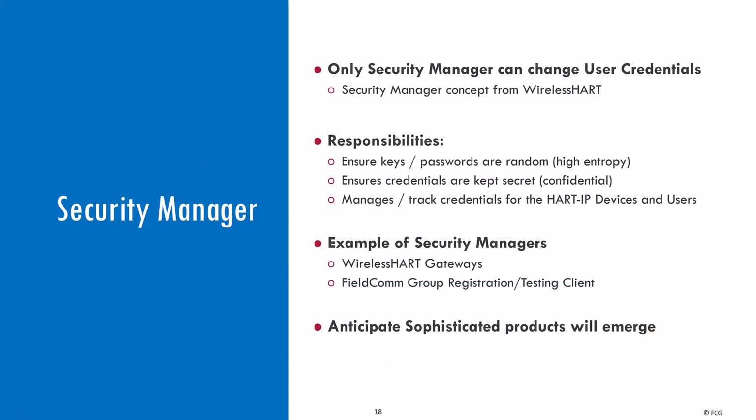We borrowed the concept of a security manager from WirelessHART. The security manager is the first set of credentials in the list found in the field device, and only the security manager can change the user credentials. Security managers manage keys and create keys, make sure they're random, make sure the keys are kept secret, track the credentials for users, and track which users have access to which devices.